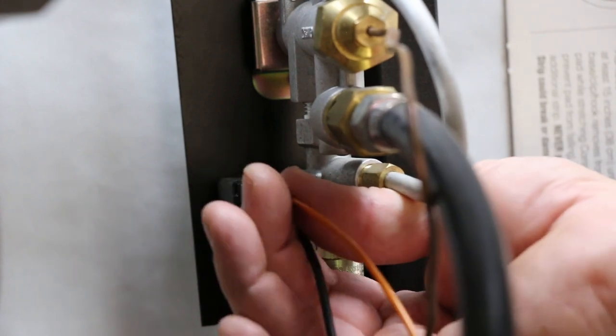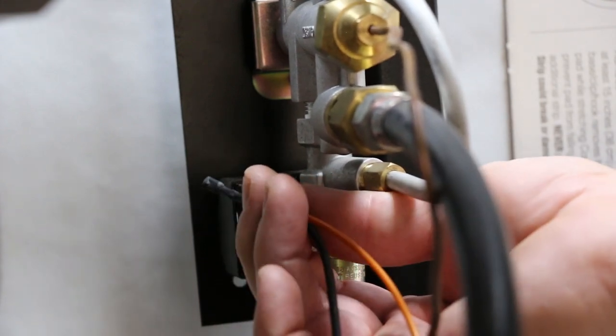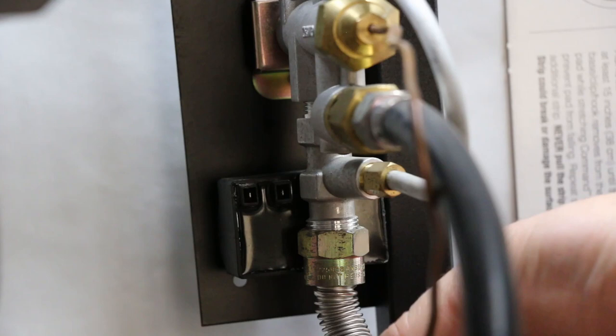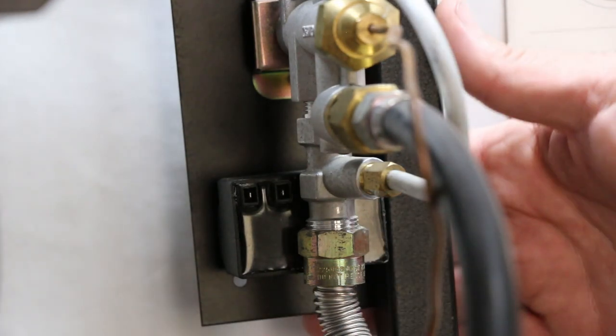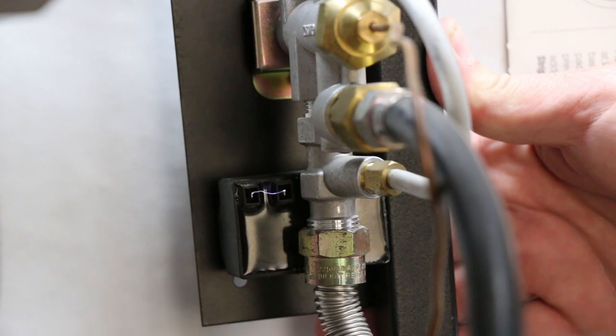If you still hear the spark but do not see the spark, disconnect the wires from the sparker again. Depress the sparker and inspect the back side of the sparker box. You should be able to see the spark arcing between terminals on the back side of the sparker. If not, replace the sparker.